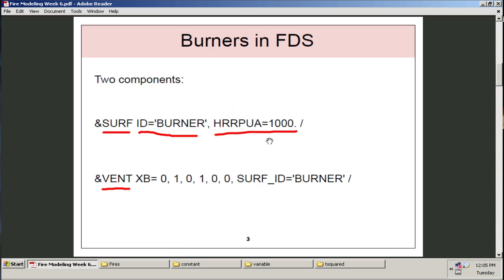That's the important parameter in this namelist. It's also important that the surf ID matches here on the vent line. So you'll see they're both named burner. The second line is the vent line. This is what actually prescribes the geometry for the vent. In this case, there's six numbers. We have 0 to 1 in the x direction, 0 to 1 in the y direction. So we have a 1 by 1 meter burner, which is 1 meter squared. And it's located on a plane at 0.0. This could also be at some elevation, but since those two numbers match in the z direction, it's going to be a plane in the z direction. So we have the XB and then we have the surf ID burner. So this tells it to look for the surf that has the ID burner and use those parameters for the vent.